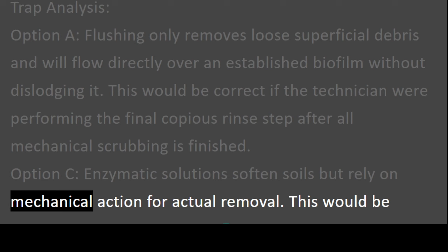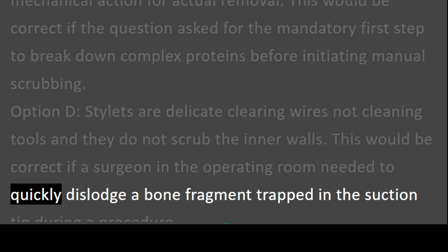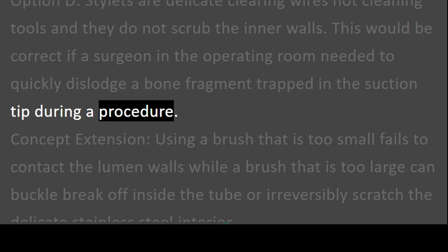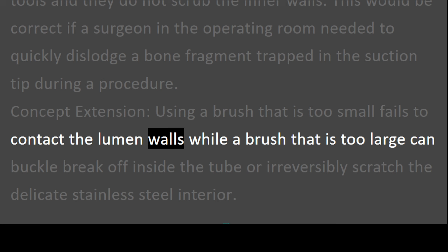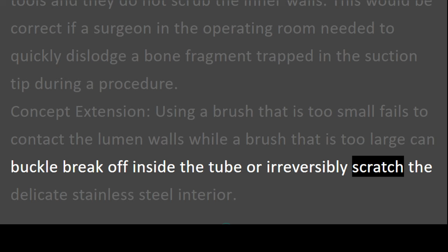manual scrubbing. Option D. Stylets are delicate clearing wires, not cleaning tools, and they do not scrub the inner walls. This would be correct if a surgeon in the operating room needed to quickly dislodge a bone fragment trapped in the suction tip during a procedure. Concept extension. Using a brush that is too small fails to contact the lumen walls, while a brush that is too large can buckle, break off inside the tube, or irreversibly scratch the delicate stainless steel interior.